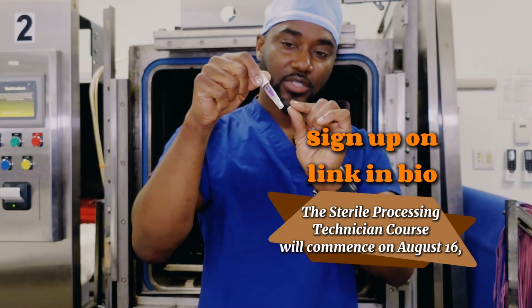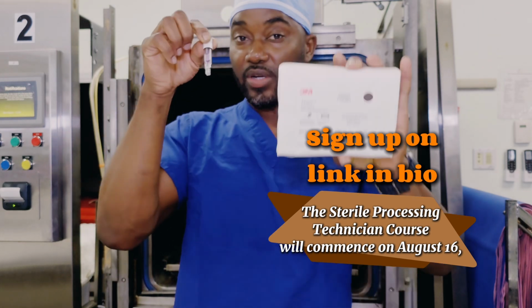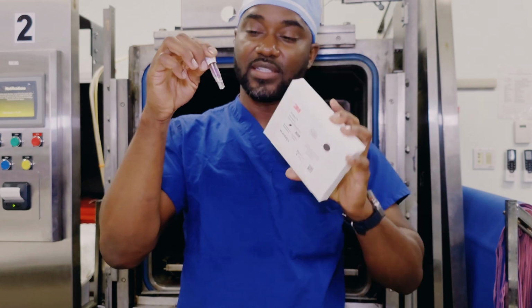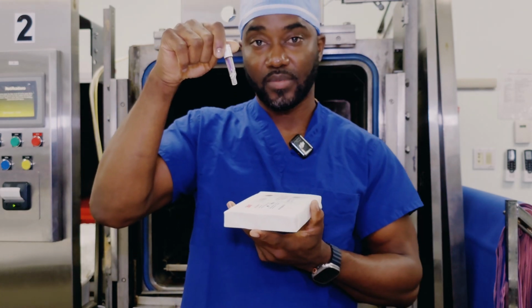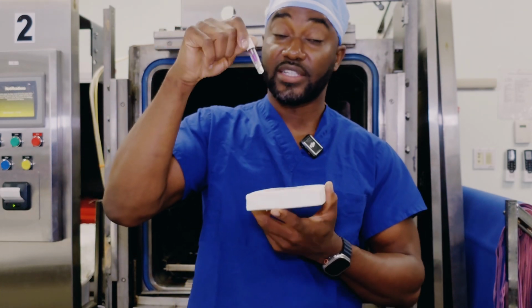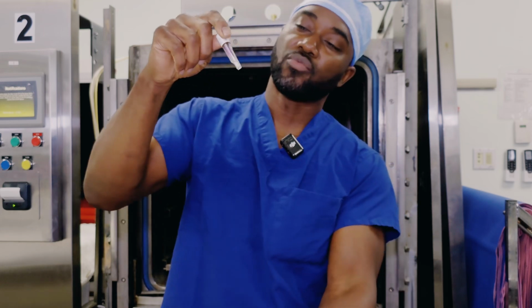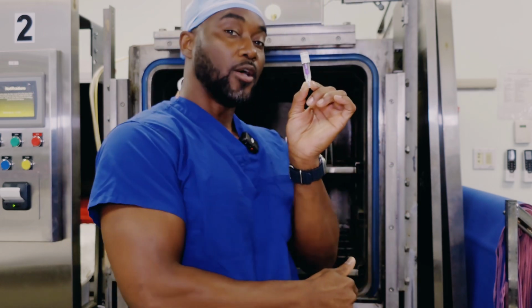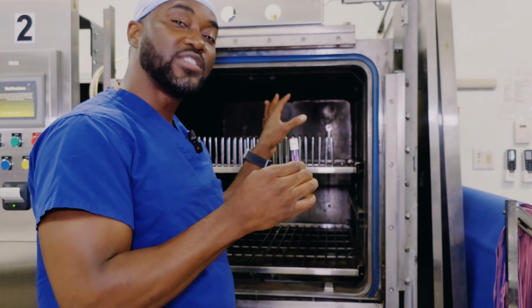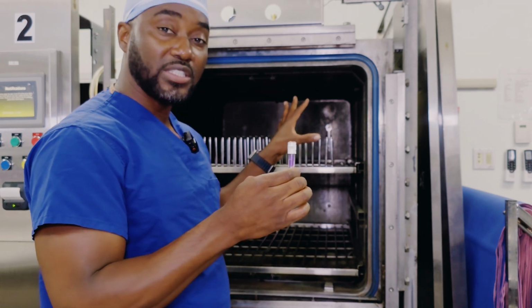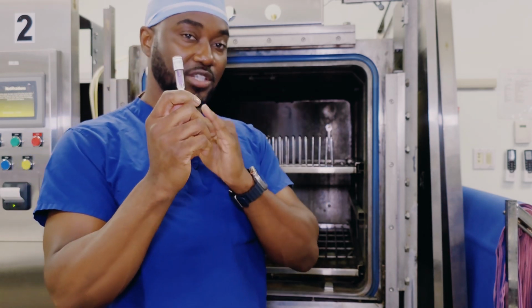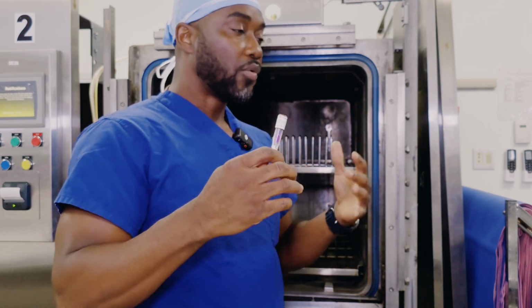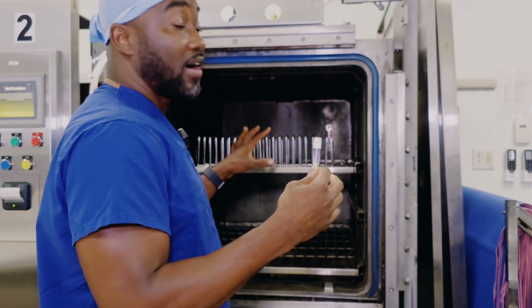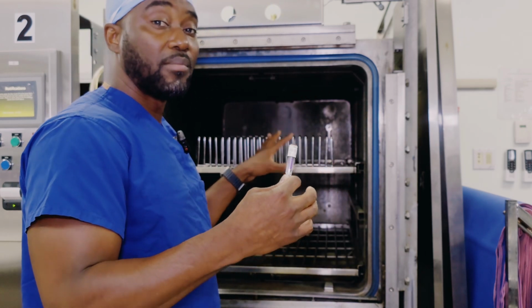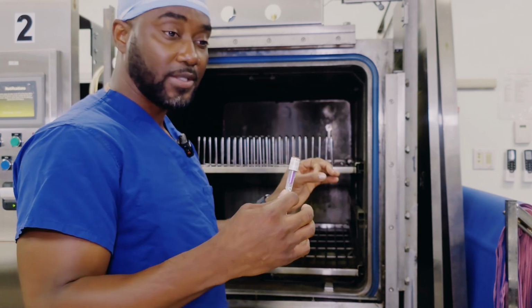With this spore, the Geobacillus embedded within this process challenge device is a heat-loving, harmless bacteria. It is the hardest to kill. The rationale of running this bacteria within your load is to measure how well the steam might kill microorganisms. And if this dies, which is the hardest to kill heat-loving bacteria, we presume that everything else in here might die along, depending if it's properly clean.